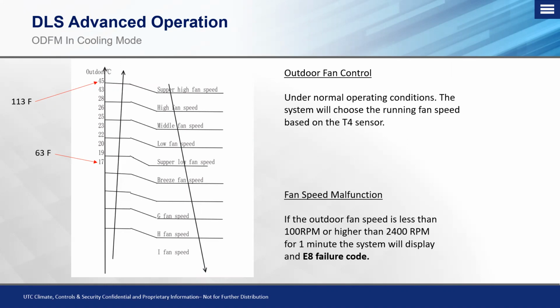If we run into a situation where the RPM feedback on the motor is out of a certain range, one of the things I do want to mention is that with the tool, we actually can see the RPM that the outdoor unit fan is running at to see if it's either too low or above a certain threshold to confirm that something's going on with that motor itself. So for the outdoor fan, if that outdoor fan speed is less than 100 RPM or higher than 2400 RPM for 1 minute, the system will display an E8 failure code, which is a fan speed out of control.